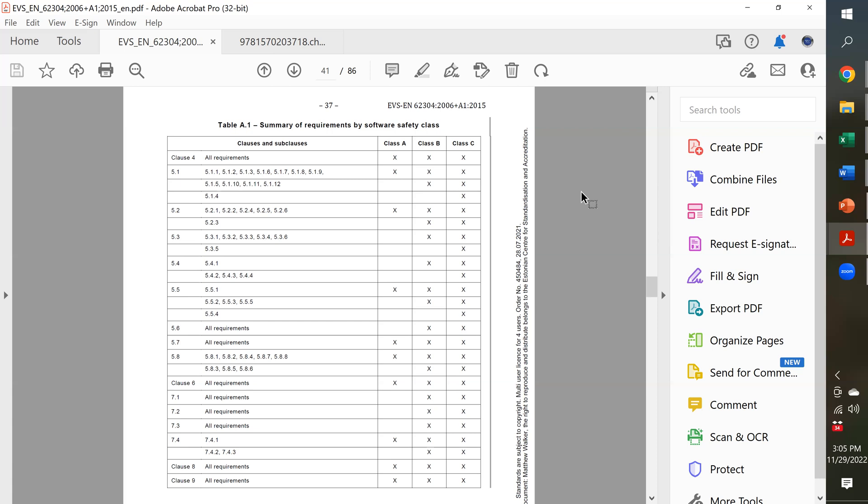So, if you're not familiar with this guidance document and you're working on a Class C, you've got a lot of work to do. But that very rarely happens. The Class A, that's the lowest risk. Not all the requirements are checked off. So, there are many things that aren't required for a Class A device. These are the lowest risks. The definition says for Class A that it can't cause any harm.